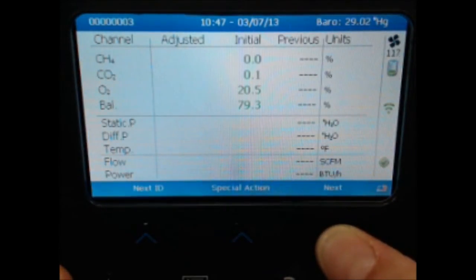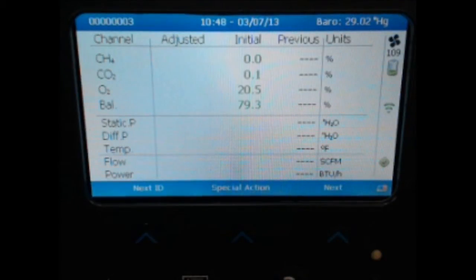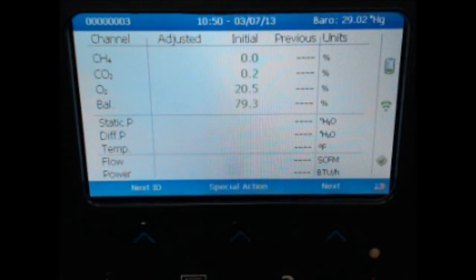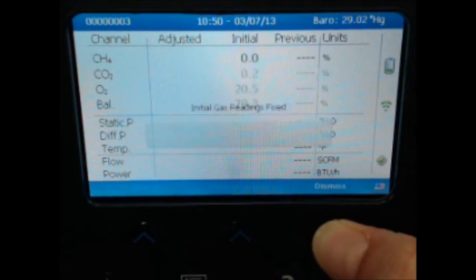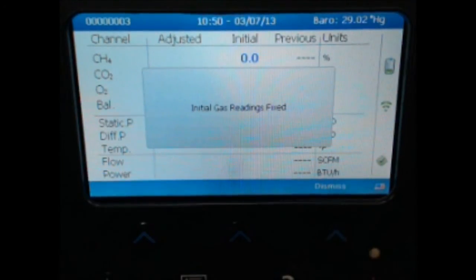The instrument will begin sampling using the pump for the indicated sampling time on the ID. Wait for the pump to complete. As the pump cycle comes to completion, your gas sample will be stabilized. Once complete and the pump stops, select next and that will lock your initial gas readings.